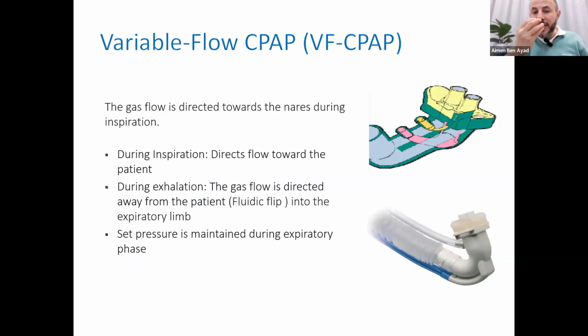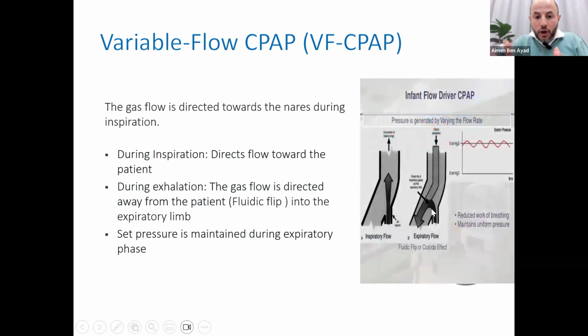So when you place the nasal mask CPAP or nasal prongs, you have a constant flow. If any one of you has used it, if you put it in the nose, it's annoying, because during inspiration and expiration, when you exhale, you feel something coming inside your nose. So it takes time to adjust to it. Versus if you use variable flow, during inspiration, the flow is directed toward the patient. But during expiration, the valve is open, and part of the flow gets away from the baby.